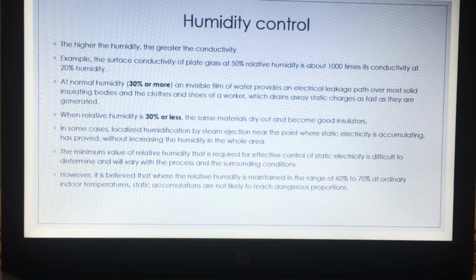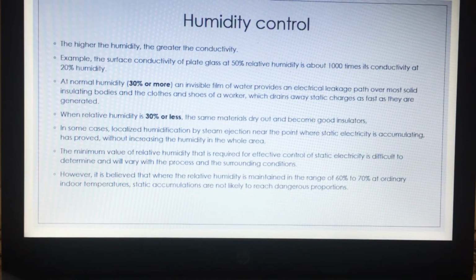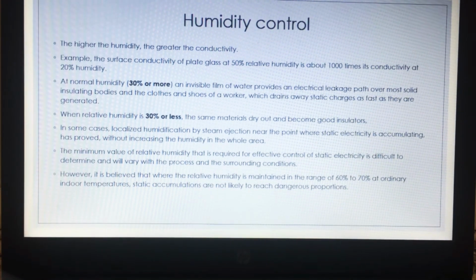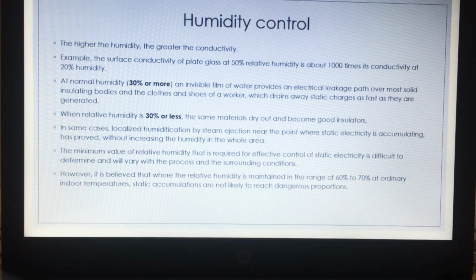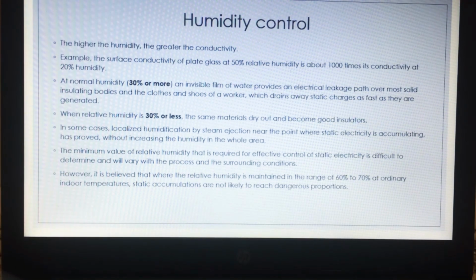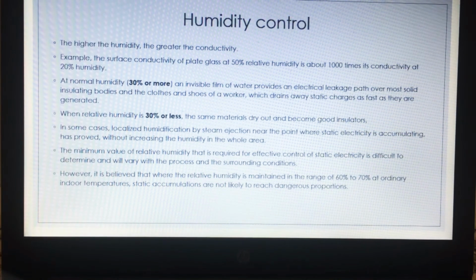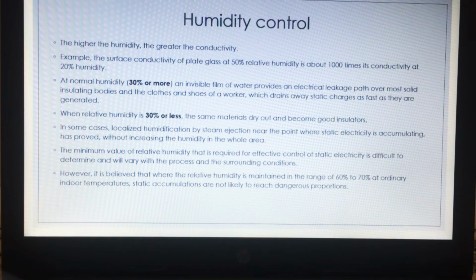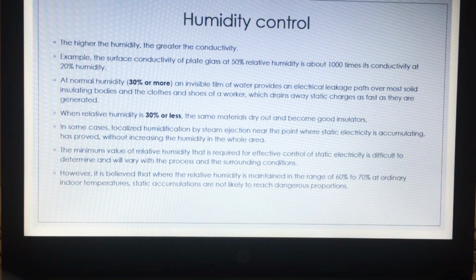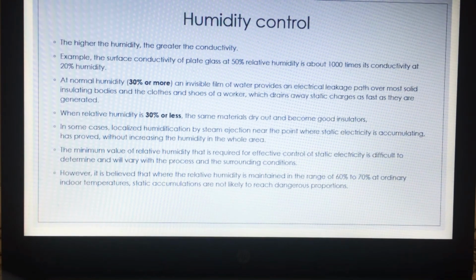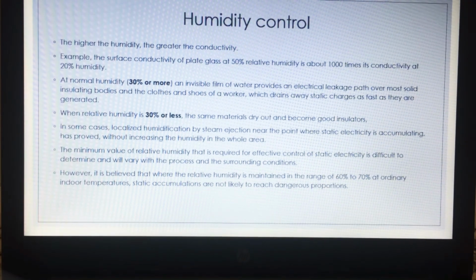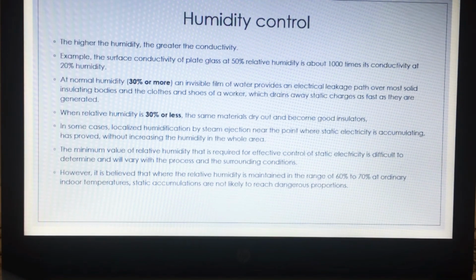When relative humidity is 30% or less, the same materials dry out and become good insulators. In some cases, localized humidification by steam injection near the point where static electricity is accumulating has proved effective without increasing the humidity in the whole area. The minimum value of relative humidity required for effective control of static electricity is difficult to determine and will vary with the process and the surrounding conditions. However, it is believed that where the relative humidity is maintained in the range of 60% to 70% at ordinary indoor temperature, static accumulations are not likely to reach dangerous proportions.